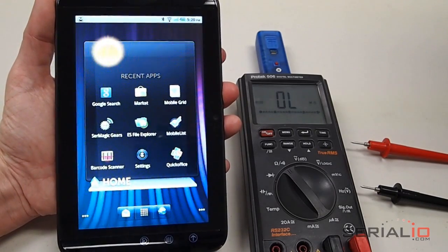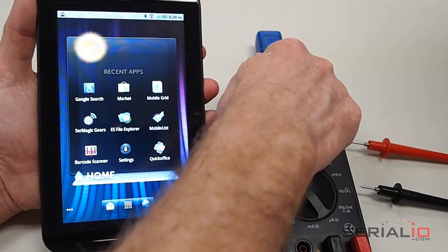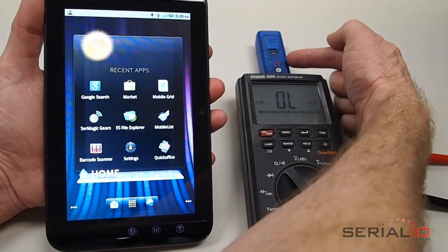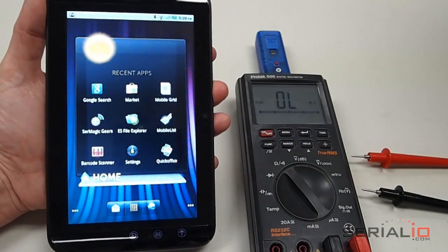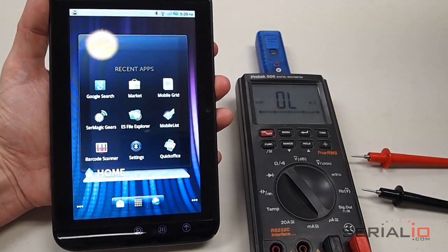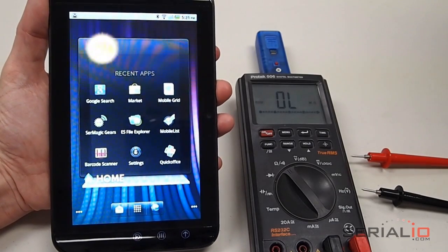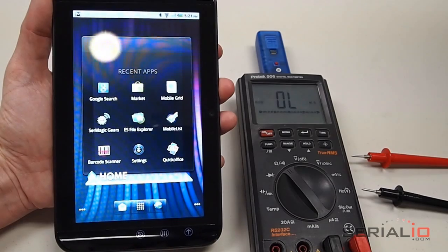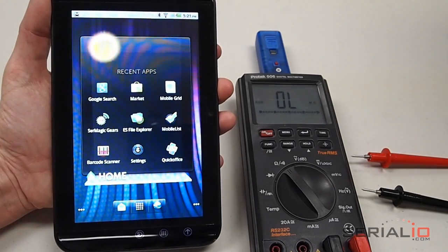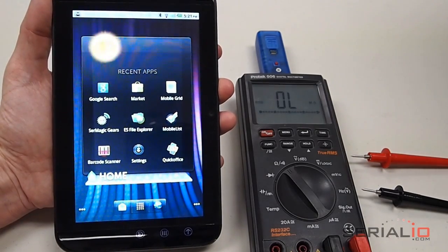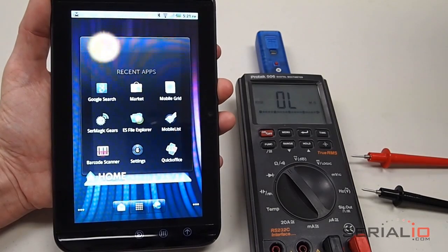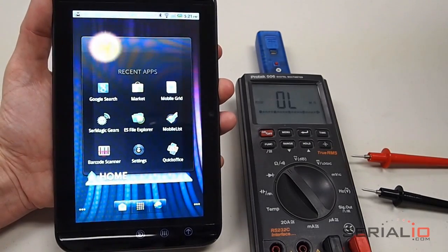First, you set up your BlueSnap AAA serial adapter for the digital equipment settings. In this case, the meter uses 1200 bits per second, even parity, and 7 data bits. These commands can be set using one of serialio.com's BlueSnap setup tools or with a terminal program connected on the BlueSnap serial port. The BlueSnap is connected to the meter's serial port.